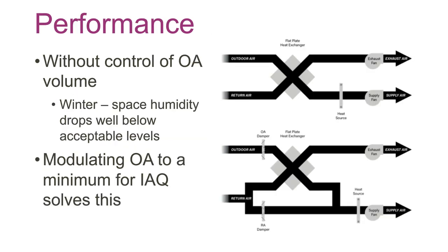However, 100% outside air isn't really a great idea. If you don't control the volume of the outside air, as we mentioned earlier, your RH in your space is going to go way, way too low in the wintertime. So the bottom schematic is the one that is more often done, and that's modulating outside air from whatever the minimum is set for IAQ in the air quality, and then modulate it up from there.